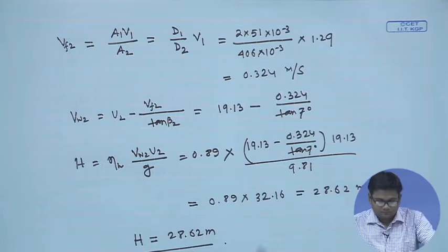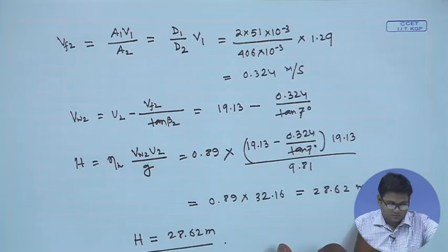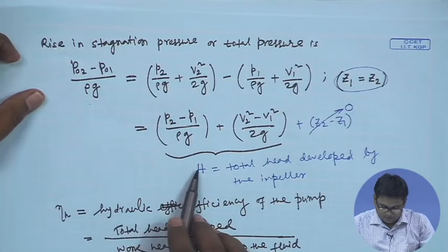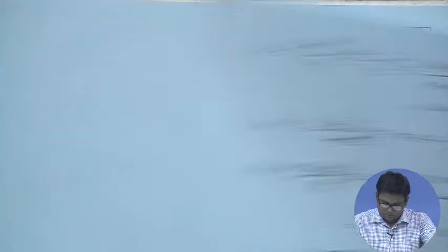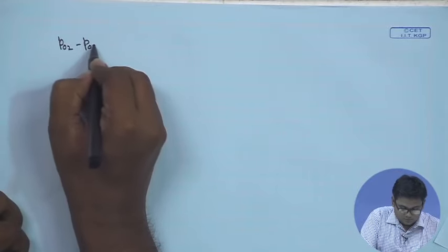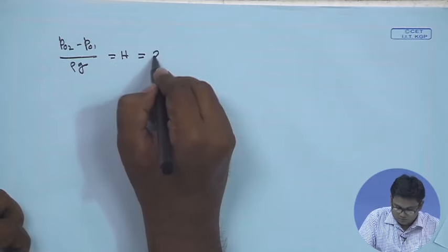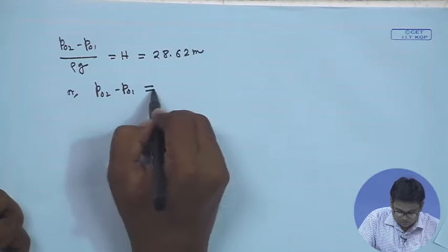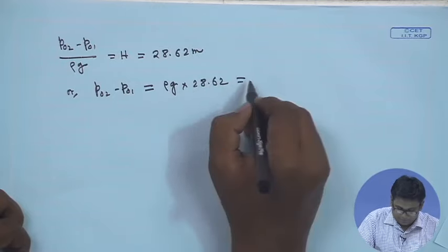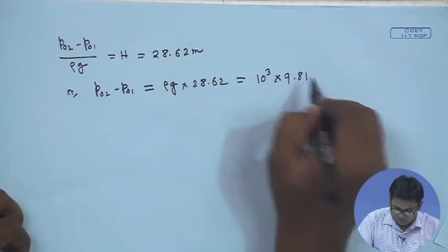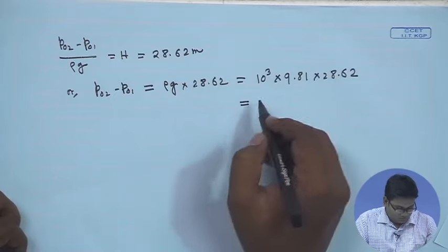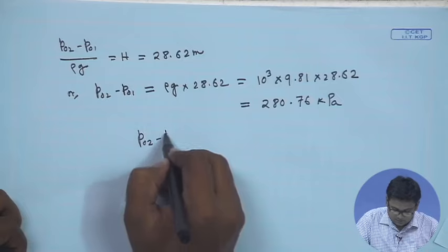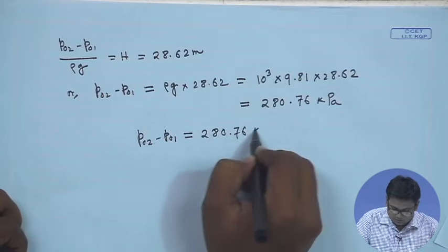The rise in stagnation pressure head equals the total head developed by the impeller. So (p02 - p01)/ρg = H = 28.62 m, giving p02 - p01 = ρg × 28.62 = 1000 × 9.81 × 28.62 = 280.76 kPa. The rise in stagnation pressure across the impeller is 280.76 kPa.